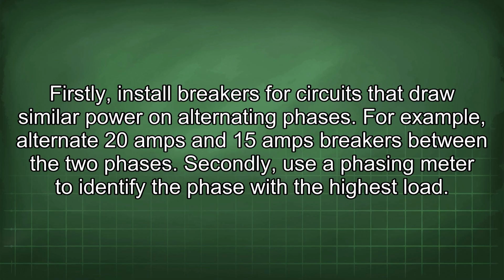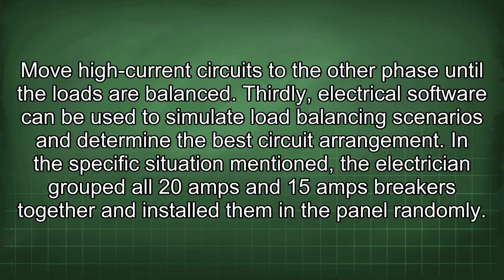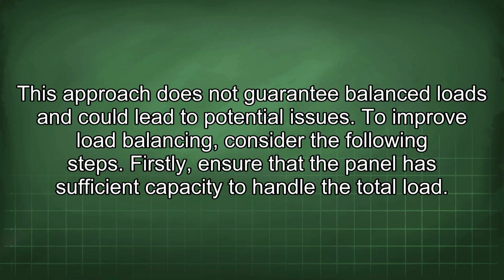Secondly, use a phasing meter to identify the phase with the highest load. Move high current circuits to the other phase until the loads are balanced. Thirdly, electrical software can be used to simulate load balancing scenarios and determine the best circuit arrangement. In the specific situation mentioned, the electrician grouped all 20 amps and 15 amps breakers together and installed them in the panel randomly. This approach does not guarantee balanced loads and could lead to potential issues.